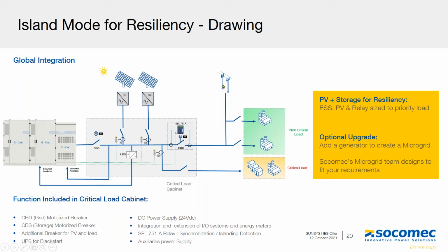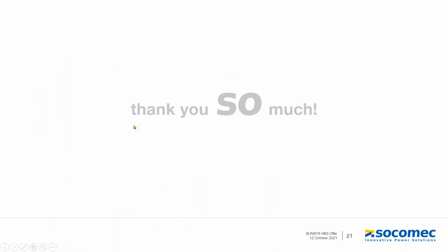So just imagine, the mains fail. What we have is a relay that senses the grid is down. It opens a motorized breaker. There's data communication to our control computer, and we'll switch operating modes and operate the system in off-grid mode. What's in this gray box is different in size depending on the interconnection of the building, the size of a half dozen different things. So every one of these is a little bit different, but we'll help you design whatever this is for your project.